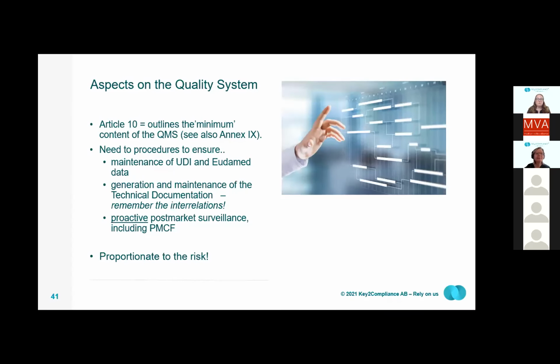Of course, you would also need to update your QMS so that it relates to the MDR. Article 10 outlines the minimum content of your QMS. So you need to update your QMS to ensure, for example, maintenance of the UDI and UDI-related data, the generation and maintenance of technical documentation, and do not forget all the interrelations that we just talked about, and proactive post-market surveillance, including post-market clinical follow-up.